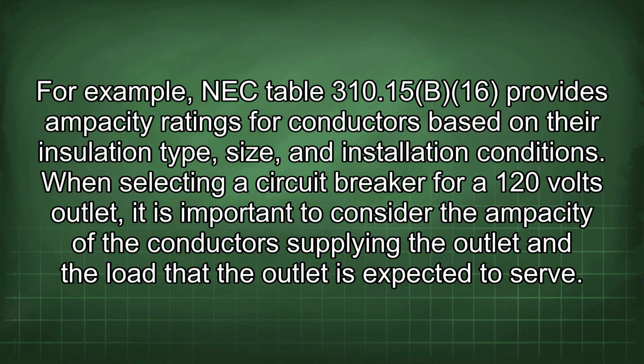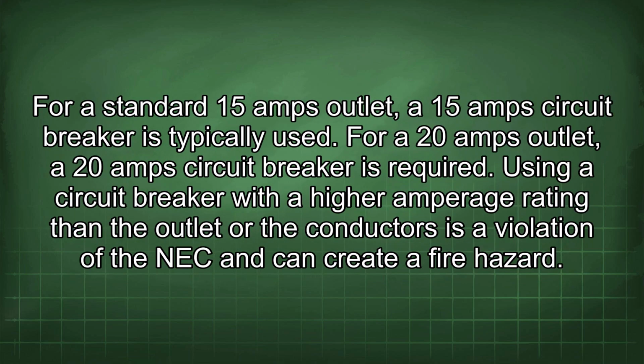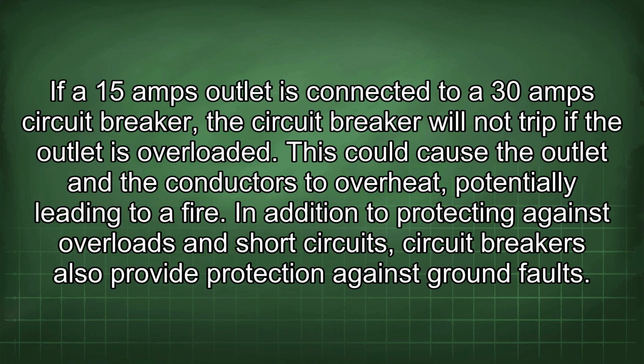When selecting a circuit breaker for a 120 volt outlet, it is important to consider the ampacity of the conductor supplying the outlet and the load that the outlet is expected to serve. For a standard 15 amp outlet, a 15 amp circuit breaker is typically used. For a 20 amp outlet, a 20 amp circuit breaker is required. Using a circuit breaker with a higher amperage rating than the outlet or the conductors is a violation of the NEC and can create a fire hazard. If a 15 amp outlet is connected to a 30 amp circuit breaker, the circuit breaker will not trip if the outlet is overloaded. This could cause the outlet and the conductors to overheat, potentially leading to a fire.